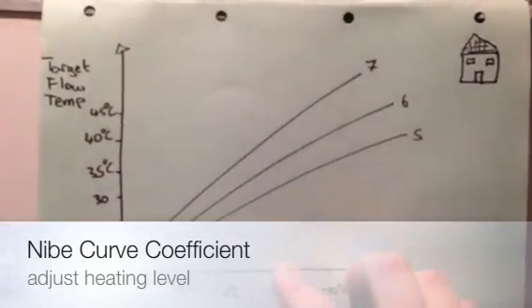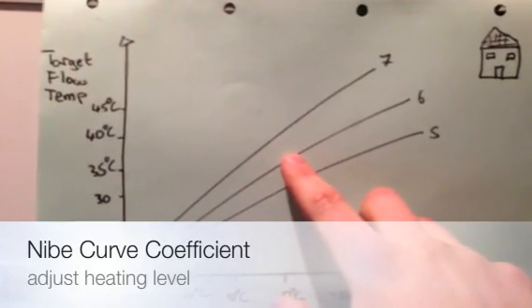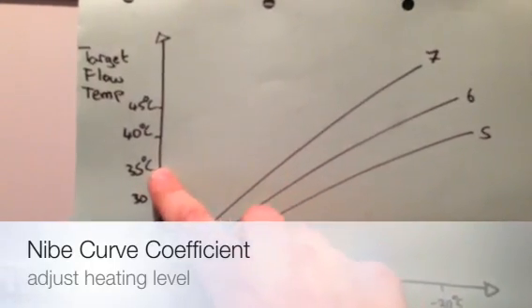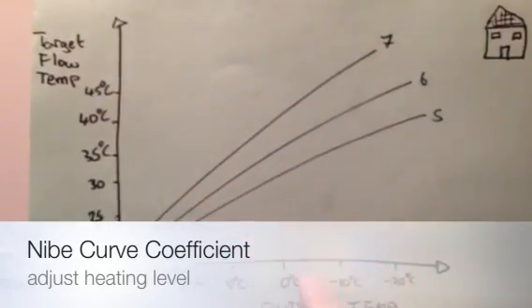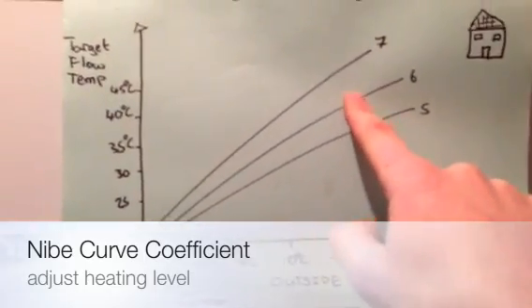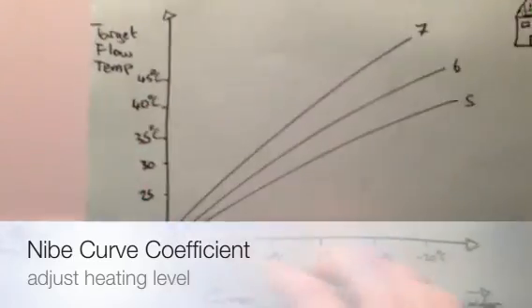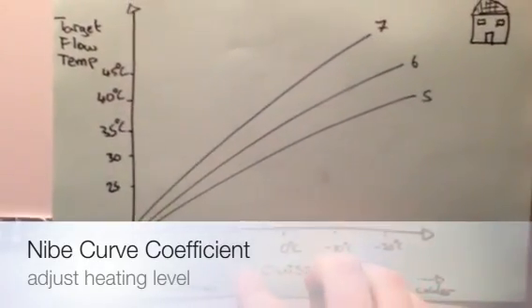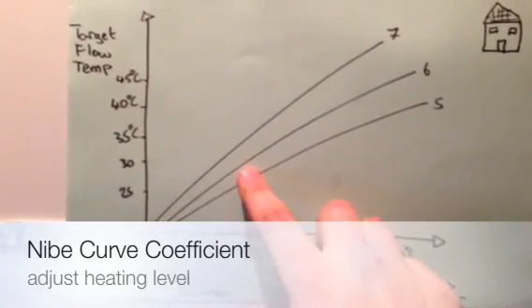For example's sake, at 0 degrees outside on curve coefficient 6, we're looking for 35 degrees to go into the building. As it gets colder outside, we look for a higher temperature to go into the building. As it gets warmer outside, we look for a lower temperature to go into the building.